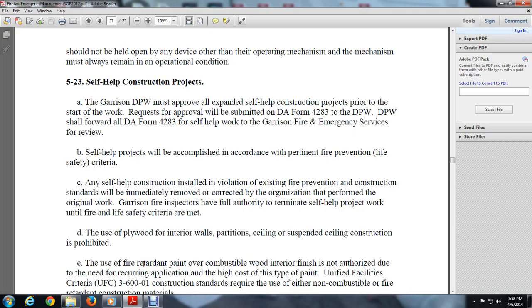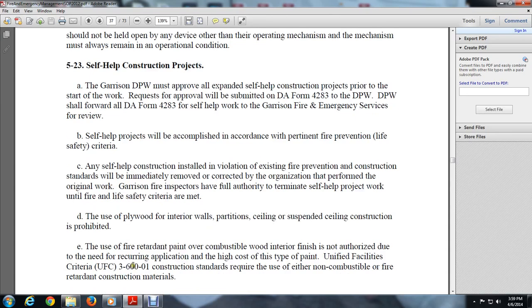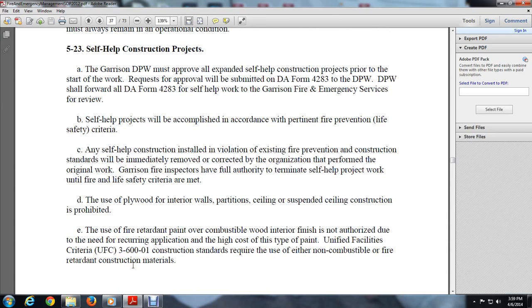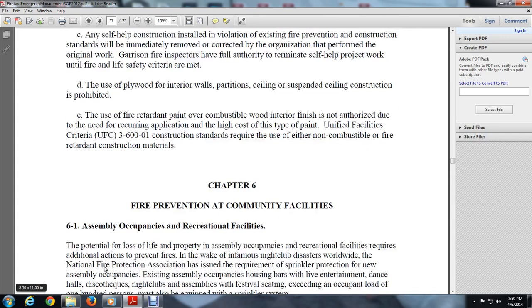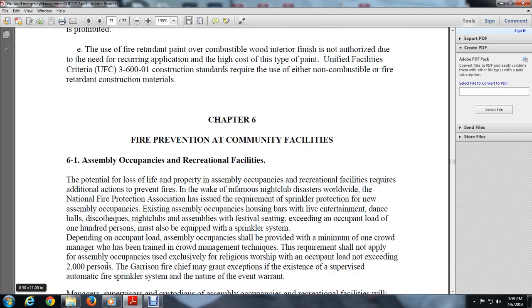The use of plywood in interior walls, partitions, ceilings, and suspended ceiling construction is prohibited. The use of fire retardant paint over combustible wood interior finish is not authorized due to the need for recurring application, and the type of paint is high cost. The Unified Facilities Criteria 3-600-01 standard construction standards require either non-combustible or fire retardant construction materials. Chapter 6, Fire Prevention and Community Facilities.